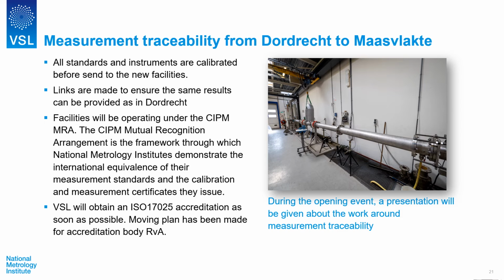How do we do that? We also asked the manufacturers to calibrate the instruments, and we also made a link, for example, with the largest Coriolis meters to our colleagues in Germany at PTB. That means we have a triangular, or maybe even more, connection, so that if we leave the Dordrecht office and cannot calibrate that anymore, we still have a link because we already know the differences between PTB, the manufacturer, and our old facility.